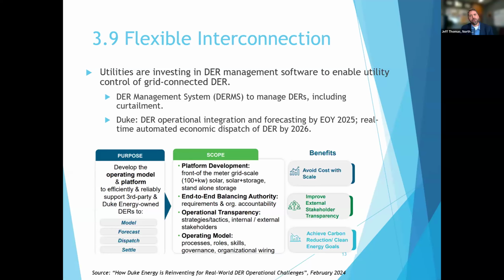Part of this flexible interconnection involves real-time curtailment and being able to study all these facilities. The DER dispatch tool and DERMS, the DR management software, rolling that out and allowing the utility to have more direct control over the DERs on the grid is really critical to that effort. If we're going to see a lot more projects connected under provisional or ERIS in order to achieve speed of interconnection, we're going to need these capabilities to be robust.